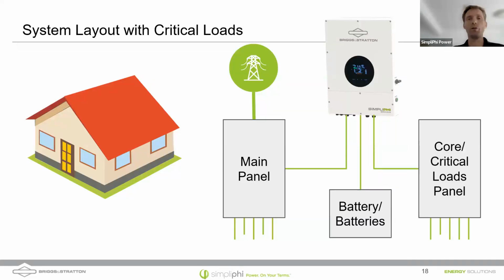So critical loads, what I'm showing here is typically just a simple single line diagram of how a Briggs & Stratton inverter or another hybrid inverter could be wired. A hybrid inverter typically has the charge controllers built into it, has the ability to connect with the grid, and has the ability to charge batteries. So typically we'll bring energy from the main panel into that inverter, and then we'll allow that inverter to back up critical loads.